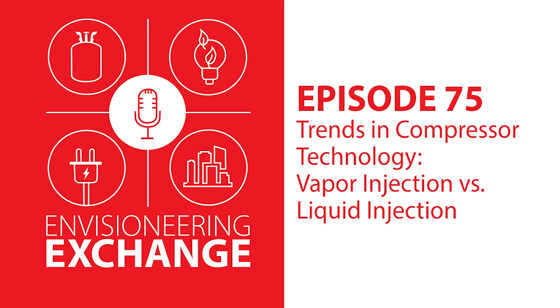So the compressor and its internals are designed to be able to achieve that wide map. Basically, the injection line is piped up to the middle portion of the scroll set, and that's where the injection occurs, for compressors that have vapor and liquid injection as well. It's a purposely designed compressor for that application. You can't take an off-the-shelf compressor and modify it. It has to be designed for injection from the get-go.